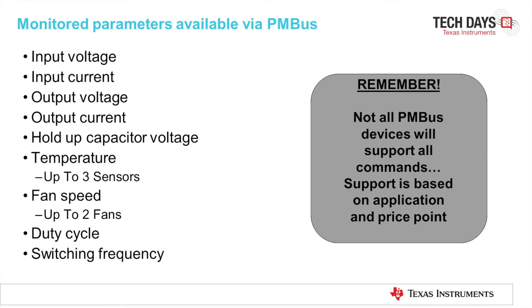There are many parameters of the power supply that can be monitored via PMBus, such as input voltage, input current, output voltage, and output current. Hold-up capacitor voltage. Temperature, up to three sensors externally. Fan speed, up to two fans. Duty cycle as well as switching frequency. Remember, not all PMBus devices will support all the commands — support is based on application and price point of the solution.